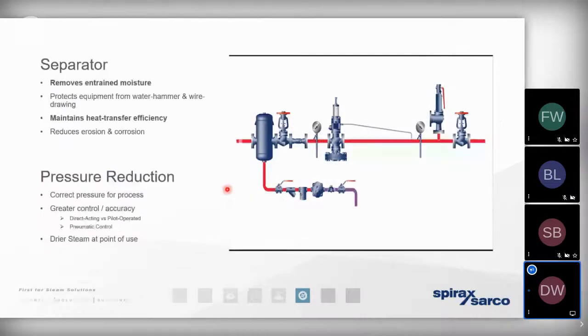We also know the benefits of keeping the steam as dry as we possibly can. The drier the steam, the more heat energy is going to be present in the steam, and the greater the rate of heat transfer is going to be. But another key benefit of drying the steam using a separator is by removing the moisture droplets, we're protecting the control valve from the risk of that erosion.